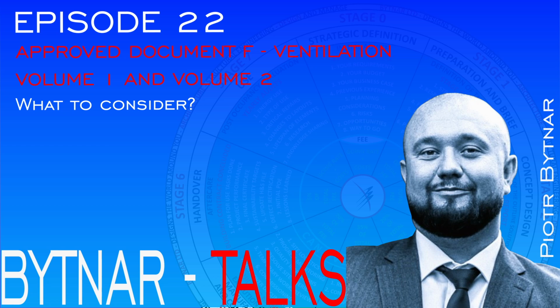Section 1 informs us of the required ventilation rates in the situation of reasonable external air quality. It is important to provide the right level of ventilation, but equally so to maintain a habitable level of noise within the dwellings, and this point concerns the ventilation units itself, the ducting, but also the noise outside. The levels should be low, at 30 decibels for noise-sensitive rooms and 45 decibels for less noise-sensitive rooms, measured to BS 8233 standard or BS EN 13141 in case of HVAC systems.